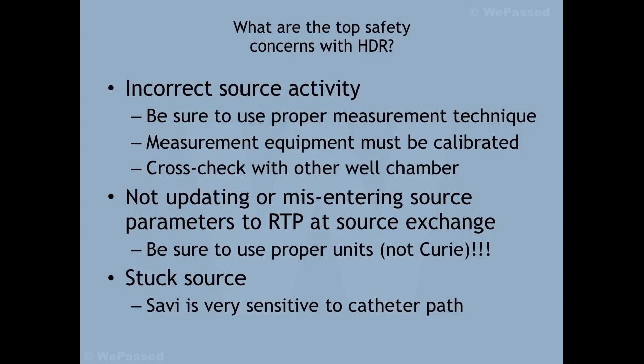For HDR, I'm really worried about the source activity. You need to make sure you measure it correctly, and your equipment is calibrated—you may cross check it if you have a different well chamber. And every time you have a new source exchange, you need to put those parameters into your treatment planning system. That number is not a Curie; you have to remember that. You need to make sure the unit is correct.